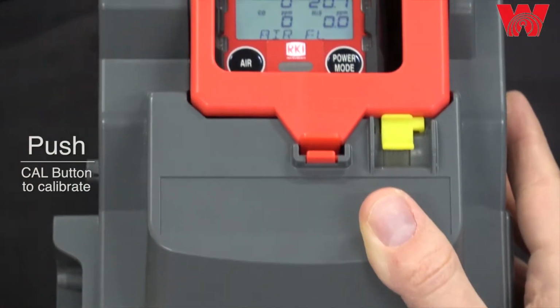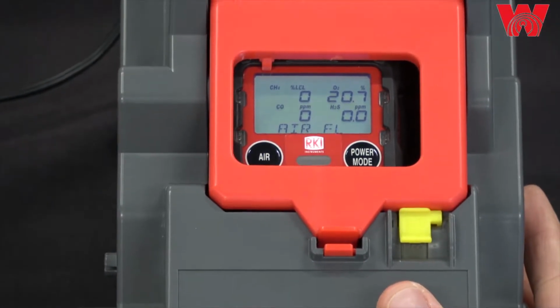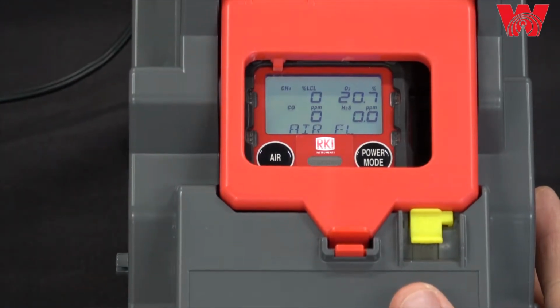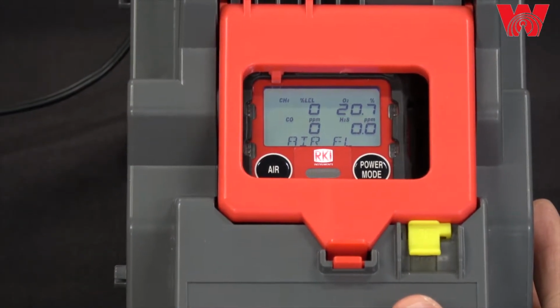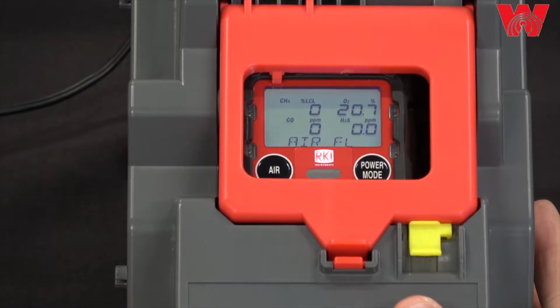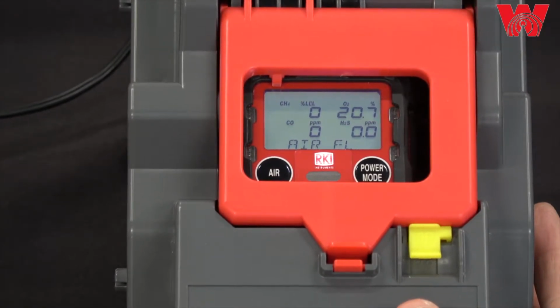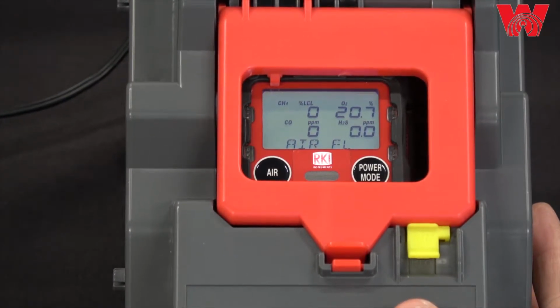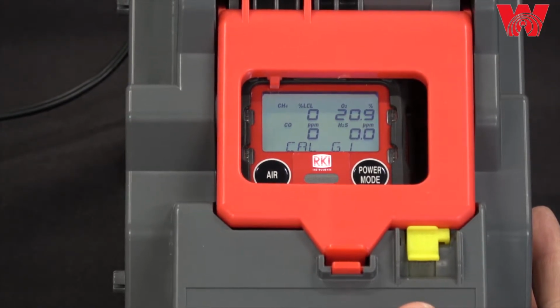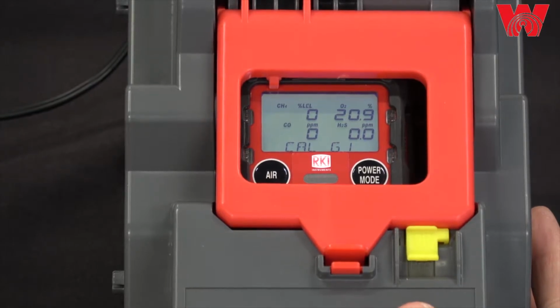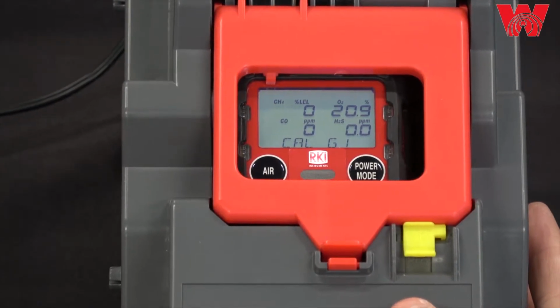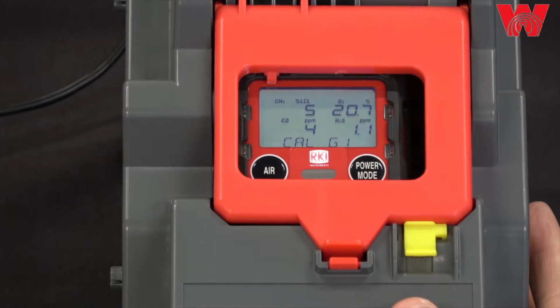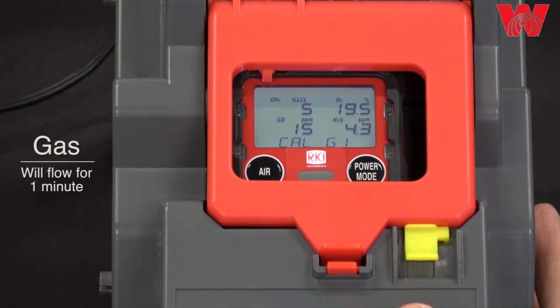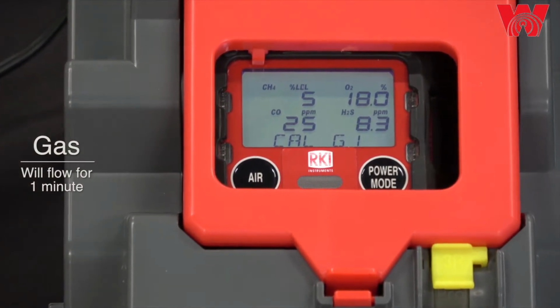Air is flowing through the air fitting. If you do not have a fresh air environment, you need to connect a cylinder of 0 air to your air fitting. But since we're in a fresh air environment here, I don't have a 0 air cylinder connected. So now it's drawing through the gas 1 fitting, it's drawing through my cylinder. It's going to draw gas for 1 minute. You can see the readings starting to change.